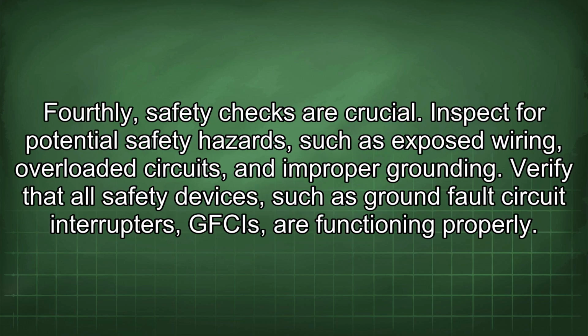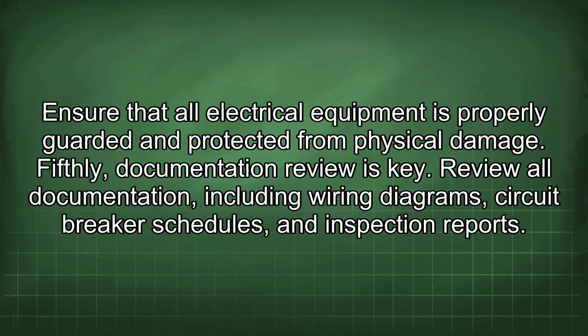Fourthly, safety checks are crucial. Inspect for potential safety hazards, such as exposed wiring, overloaded circuits, and improper grounding. Verify that all safety devices, such as ground fault circuit interrupters, GFCIs, are functioning properly. Ensure that all electrical equipment is properly guarded and protected from physical damage.